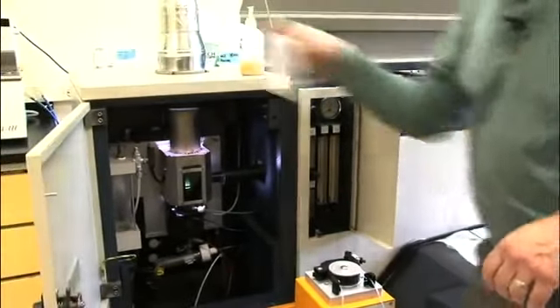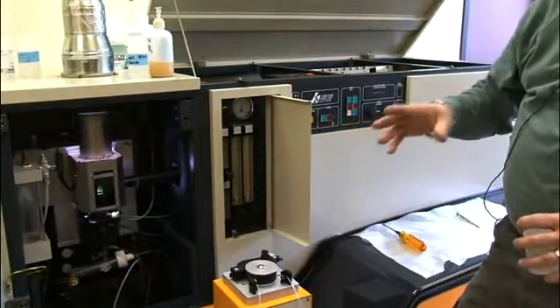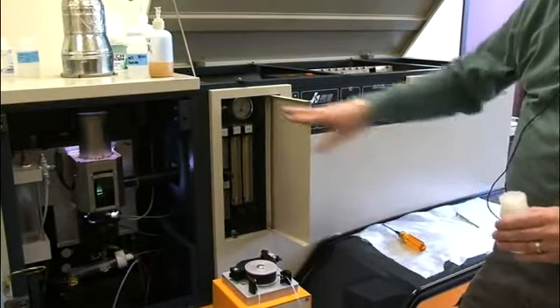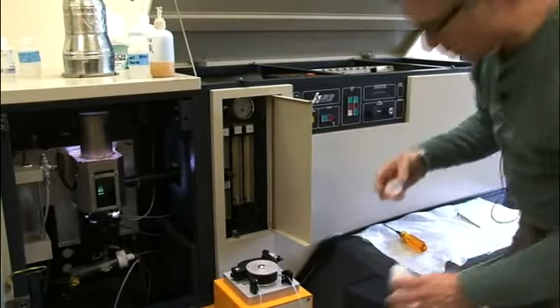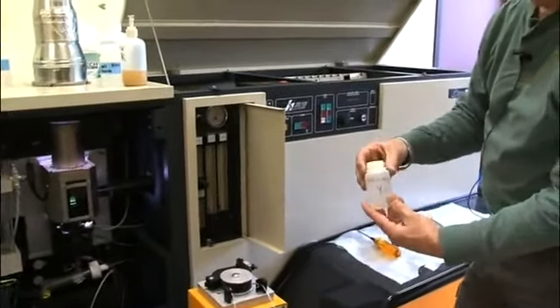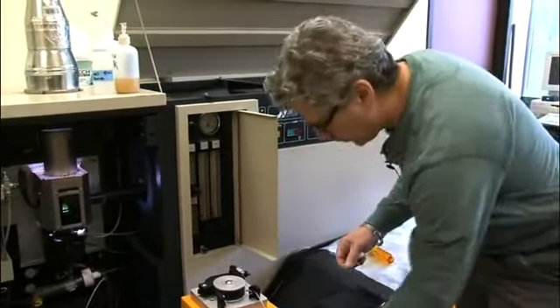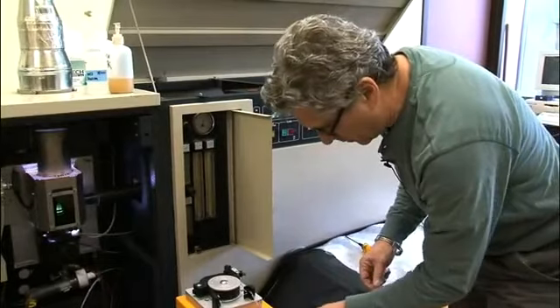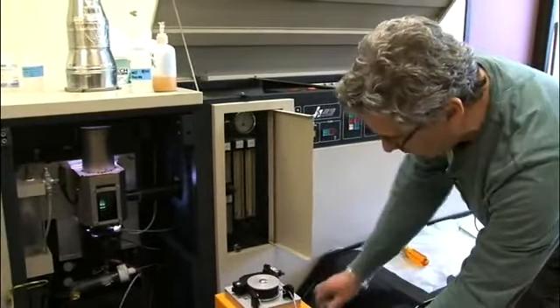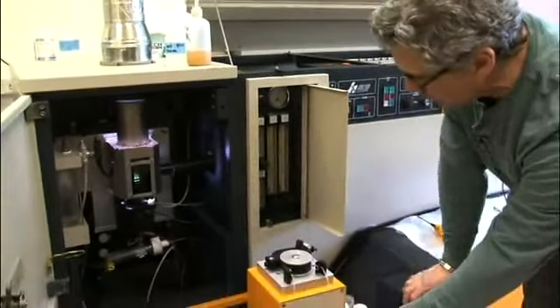One way to tell if you've changed your nebulizer or something, you want to make sure that your neb pressure is still correct if you change something. So if you put in 1,000 ppm of yttrium, there's certain colors that come out in the plasma, and that'll tell you how you can adjust your pressure.